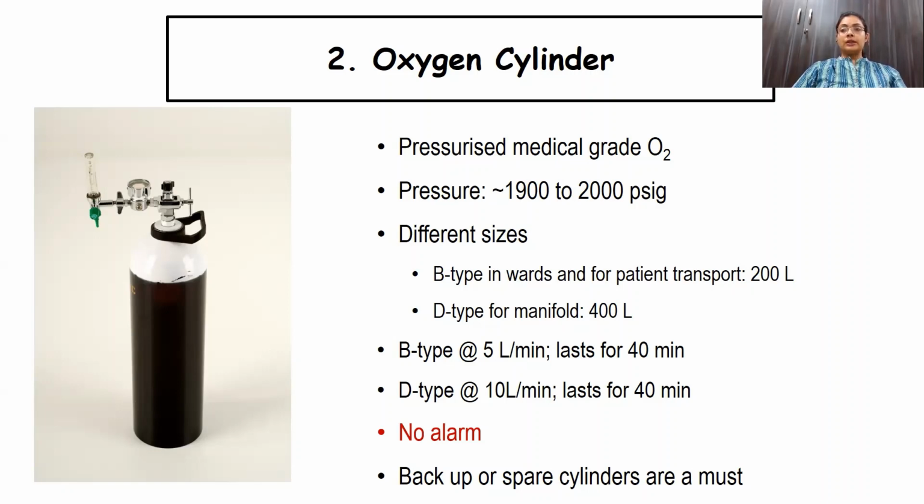Plus, another disadvantage with the oxygen cylinder is that they do not have an alarm system, unlike your pipeline supply. So, backups are essential and they are a must.